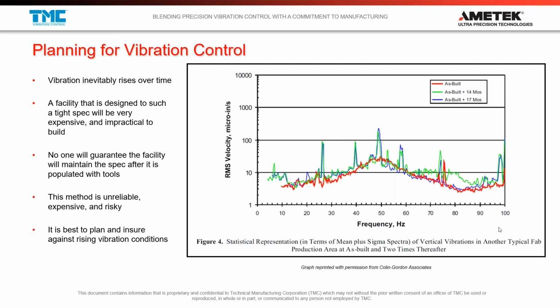And so the takeaway is, it doesn't matter how quiet your floor is, there's always, especially in a new building, as time goes on, vibration rises. And this is also true at universities. You may have a nice quiet floor in a physics lab, but then there might be construction next door that causes problems for your experiment for some long period of time.